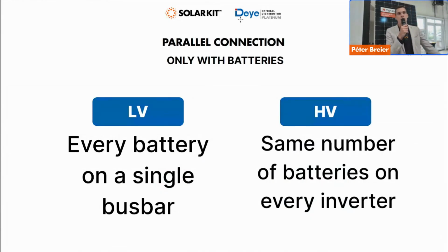When you are thinking about making parallel connections with Deye, it's a bit tricky, so please make sure to consult with us before you do that, or just be 100% sure that you read the recommended part in the user manual, because it's written there, but sometimes there is a misunderstanding. Basically, there are two very big differences between low voltage and high voltage series. First of all, every Deye needs a battery if you want to use parallel connection. That's a very important note. It's not always the case for other brands, but in Deye's case, it's always this way. So you need batteries for parallel connections.